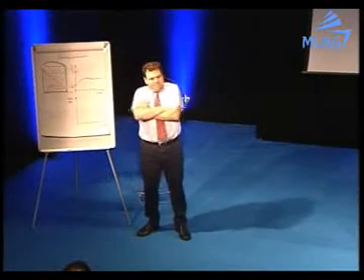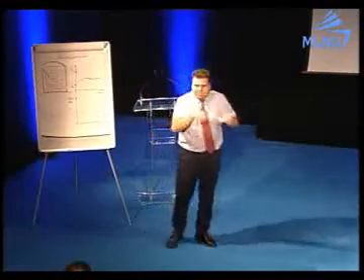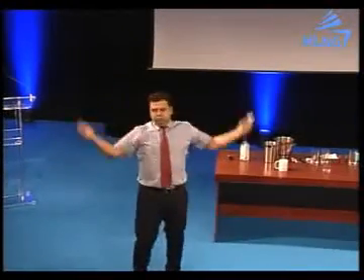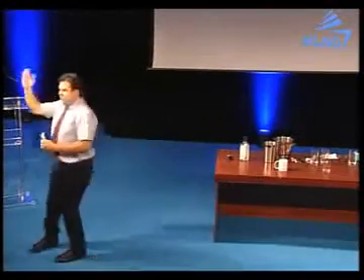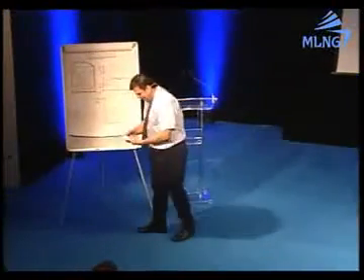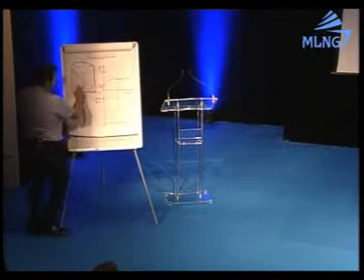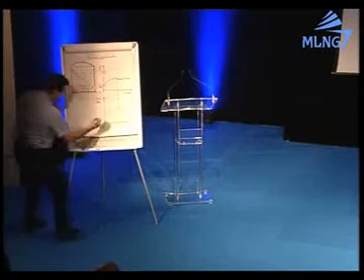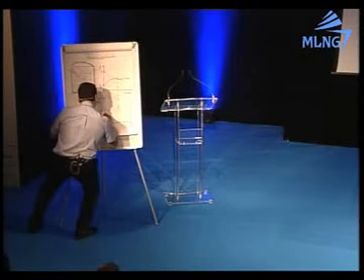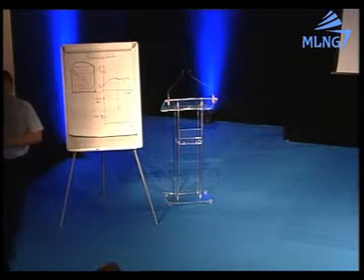You are operating tanks. You have 8 terminals like this. The operators are operating tanks, and after 3 weeks, after 1 month, suddenly, overpressure. You know the flare. We don't want that. The normal boil-off in a full containment tank is like this, 1,200 kilos per hour.